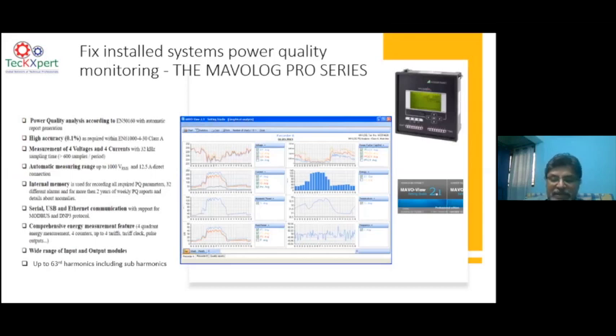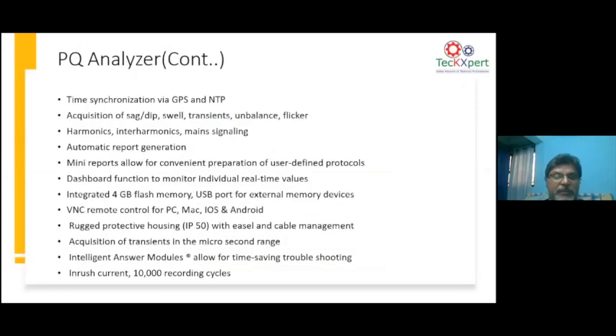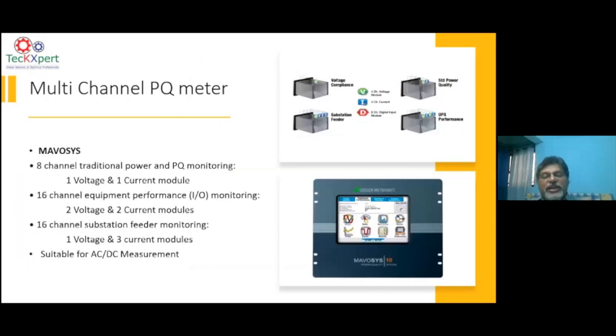There are also fixed power quality monitors that you can use. You can install these fixed power quality monitors, and this is a typical one, for continuous power quality monitoring. As you can see, it can have up to 16 channels. That means you can simultaneously monitor up to 3 feeders in a substation. You take the voltage module and 3 current modules from a single feeder, so you can monitor up to 3 feeders simultaneously with this meter. There are other power quality meters which come for single feeders also.